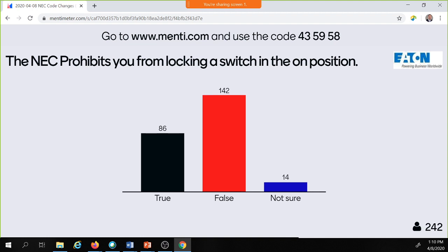This is a good one. There is now a requirement. There wasn't anything before, so the NEC didn't have any specific language. They'll always say it shall be able to be locked in the off position, but they don't say it shall only be able to be locked in the off position. So that didn't prohibit you from locking it in the on position. But the 2020 code made a change for elevators, which we're going to talk about today, where you're not permitted to have that switch able to be locked in the on position. So we're going to review that change.